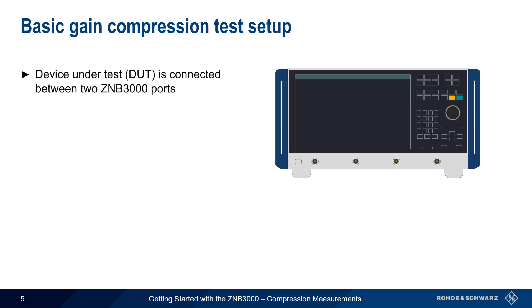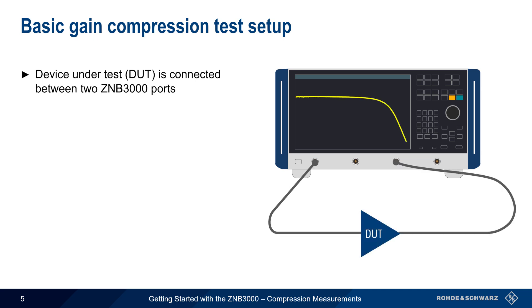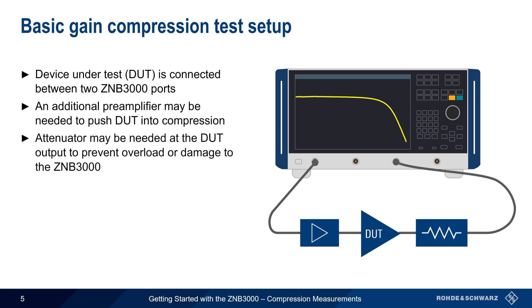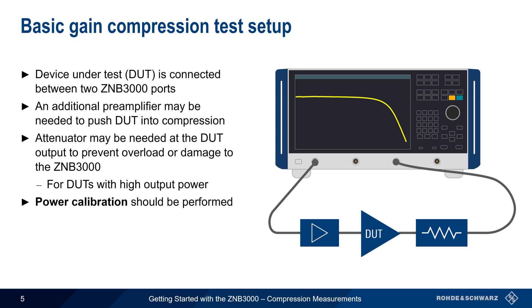The test setup for compression measurements is straightforward. The Device Under Test, or DUT, is simply connected between two ports of the ZNB3000. If the maximum output power of the ZNB3000 is not sufficient to push the DUT into compression, an additional preamplifier may be needed between the ZNB3000 output and the DUT input. At the DUT output, an attenuator may also be needed to prevent the ZNB3000 from being overloaded or damaged — particularly for DUTs that produce very high output power. A power calibration should be performed before making gain compression measurements, as it improves accuracy and can compensate for gain or loss from preamplifiers, attenuators, etc.